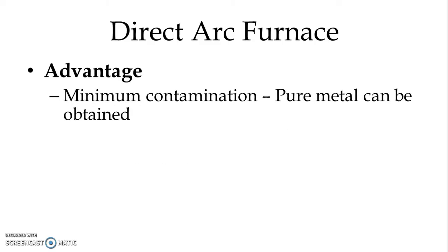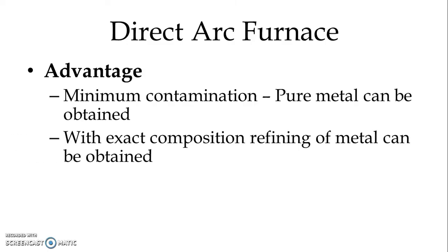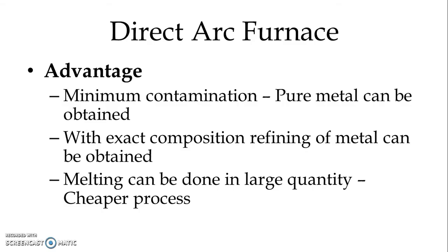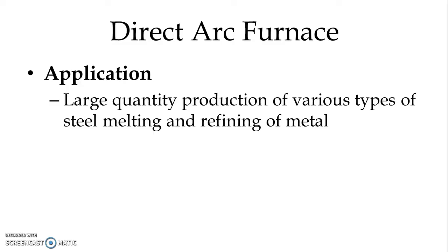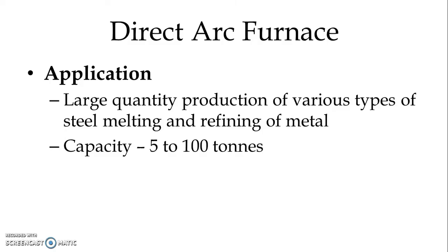High temperature is possible. Contamination is very minimum because the process is in a closed environment and oxidation is not possible, so pure metal can be obtained. With exact composition, refining of metal can be obtained. Melting can be done in large quantity and that is why the process always remains cheaper. Application of Direct Arc Furnace: because the process is cheaper and very high temperature is achieved, the application is large quantity production of various types of steel — melting and refining of metal is possible. Capacity: 5 to 100 tons.